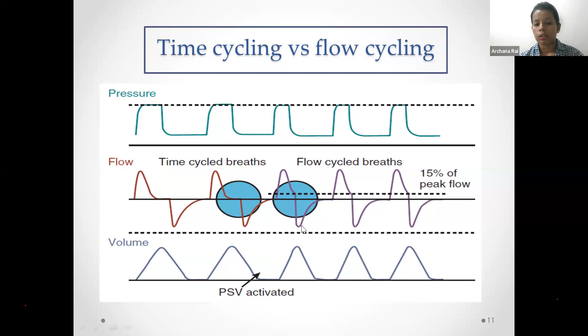So we usually set the termination sensitivity in this, which is usually between 5 to 50% and usually set at 15%. What does the termination sensitivity mean? It means that once 15% of the peak flow has been reached, the baby will go from the inspiratory phase to the expiratory phase, thereby eliminating the inspiratory hold. If we look, the inspiratory hold is not there in the flow scalar.